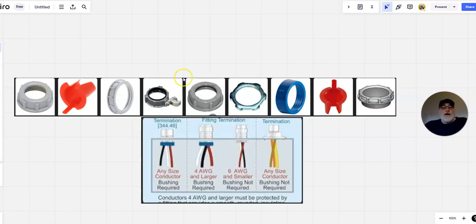Okay. Here are some examples of bushings. This is a plastic bushing that's threaded that you just roll over this connector. This is a bushing for inside of your MC to be able to separate the outer jacket, the outer flexible part of a metal clad cable, and the connection points. You always use these in MC.